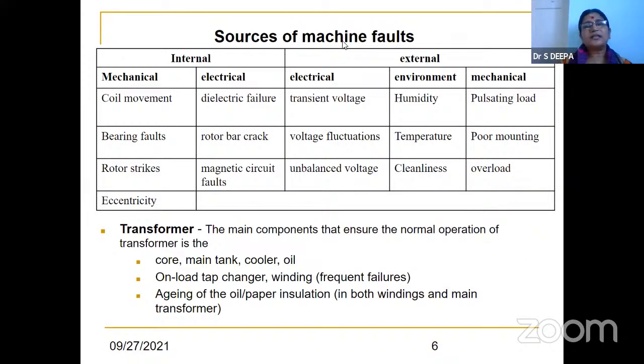What are the sources of machine fault? You will have internal and external faults, mechanical and electrical faults. In the internal, we classify the causes: moving coil movement, where the coil has shifted, bearing faults, rotor strikes and eccentricity. The electrical faults are dielectric failure, rotor bar crack, magnetic circuit faults. In the external, you have the electrical environment and mechanical faults. In electrical, the transient voltage fluctuation and unbalanced voltage. The environment means humidity, temperature, and cleanliness. Mechanical is pulsating load, poor mounting, overload. These are the types of faults that can occur in the sources of machine faults.